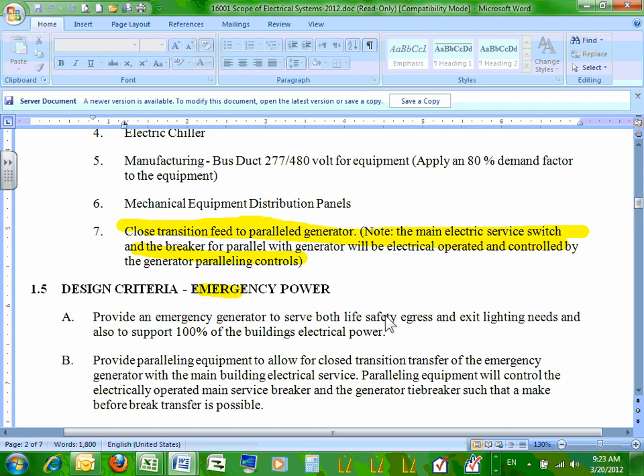So it'll fire up the generator, and it'll look at the generator sine wave, and it'll look at the utility sine wave. And it'll control the generator to the point that the generator sine wave is in sync with utility. And once my generator and my utility are in sync on their output, it will close, and that's a closed transition. So once I close on the utility, I can do a soft transfer where I can change the impedance of the genset so that my loads can slowly ramp onto the genset. Once I have my load on the genset, then I open my utility. So that's a closed transition transfer on the genset.